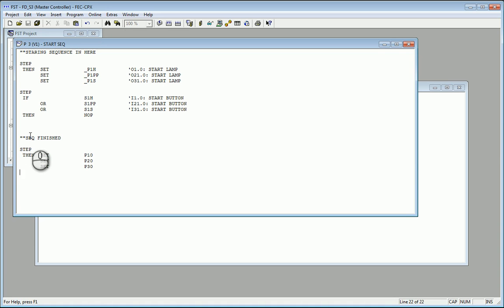No. You wouldn't set it straight after the start switch is pressed because that isn't what our starting sequence is. The starting sequence will be defined once you get the key switch. So it's a certain amount of key turning and button pressing, just to basically make you do something in the program is what it's really for. But you don't want the three programs that control the main sequence to run until it's fully started. Otherwise, when you press start, you're maybe trying to do other things, the machine's trying to run at the same time.